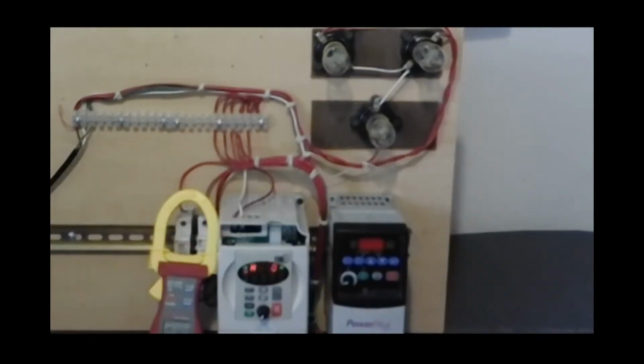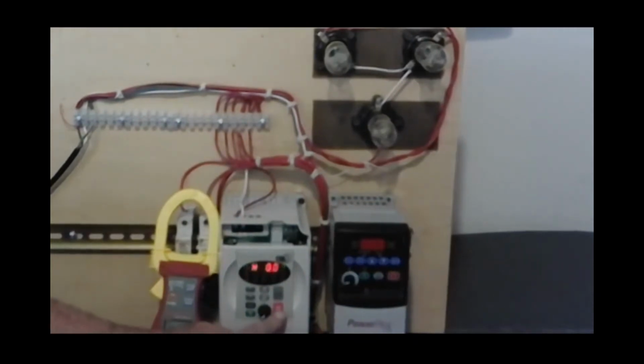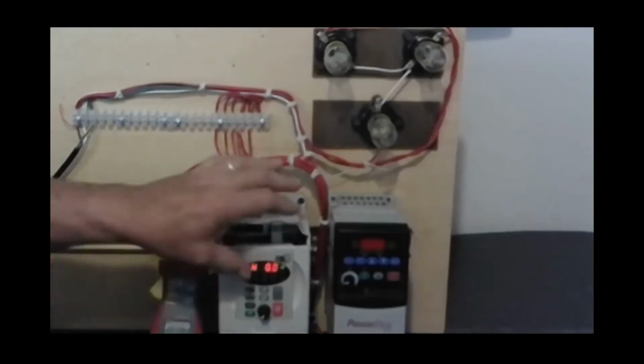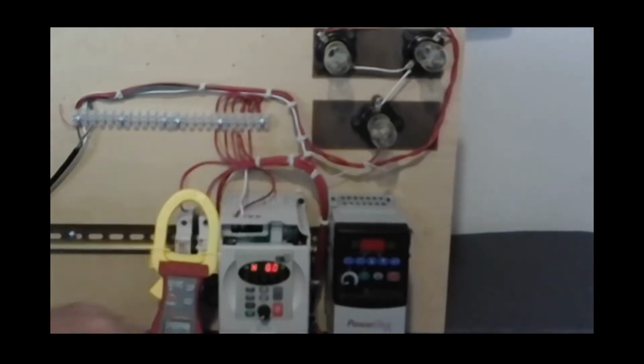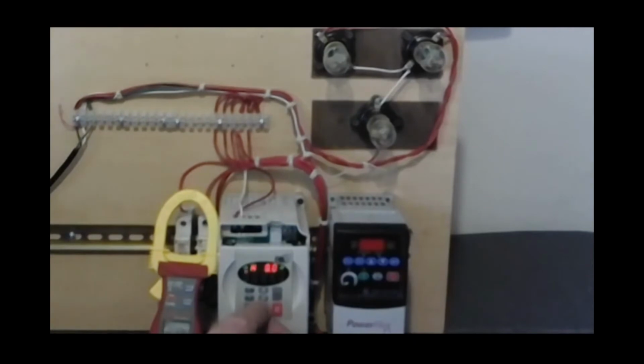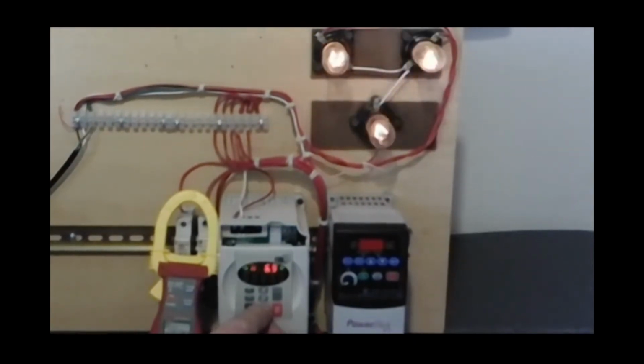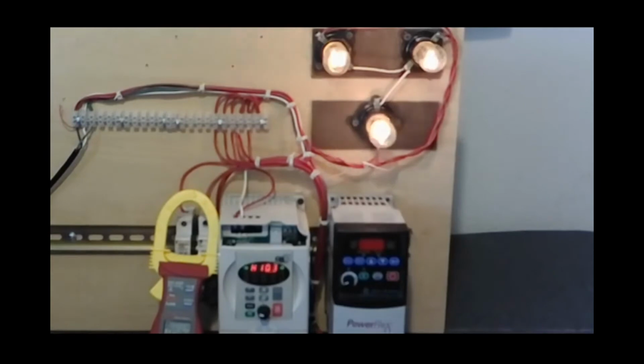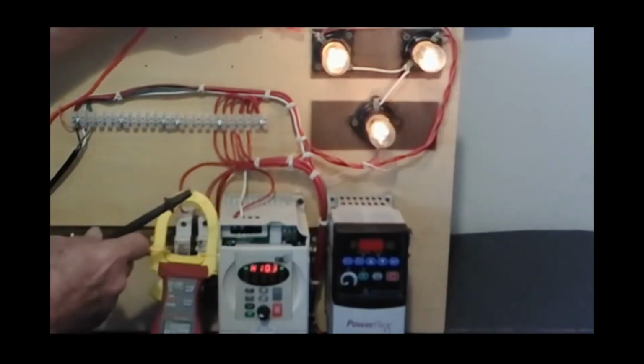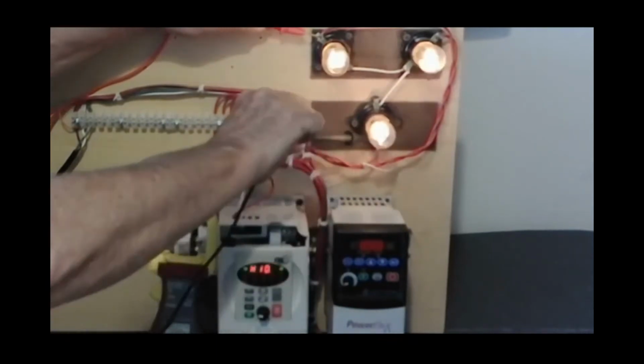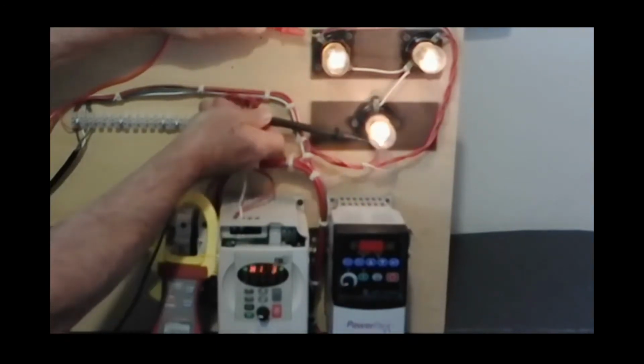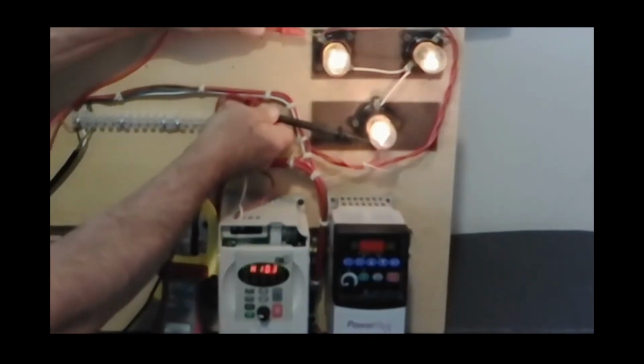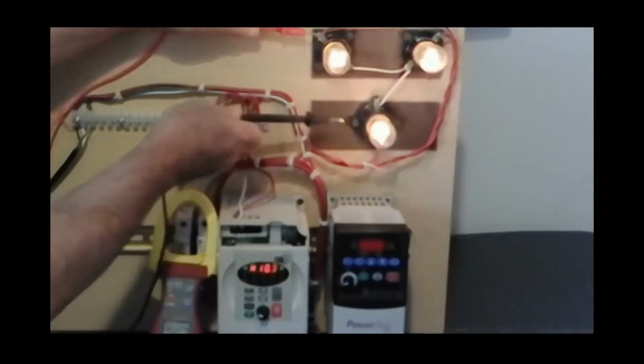Now, one of the points about this drive I've got to make, go ahead and let me turn this thing on, is we've got different types of meters here. If I turn this drive on, hit the start button, and bring up this frequency, let's go up to about 10 hertz. So I've got 10.3 hertz, that's fine. Now if I take my meter and take a measurement across the output of that drive, right there, what I'm seeing on the meter is roughly about 86 volts, 86.9, 86.8. So I do get a reading on the meter.